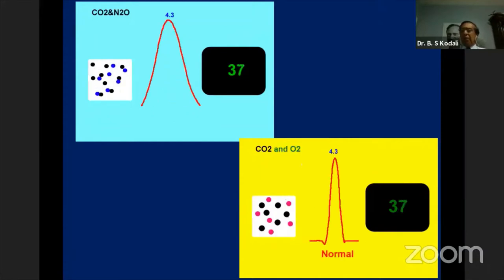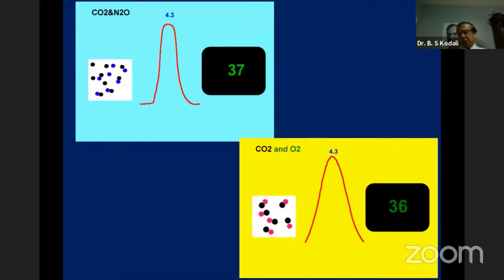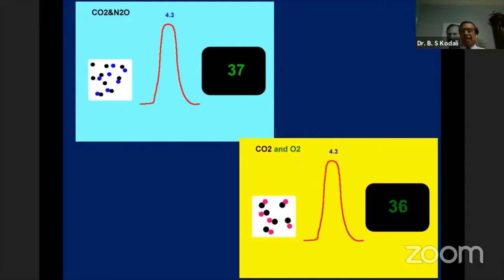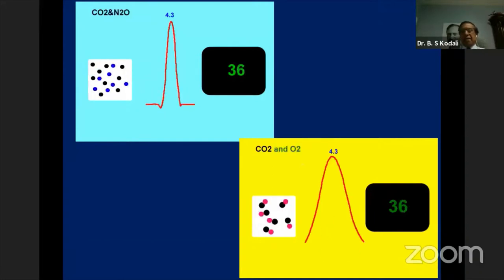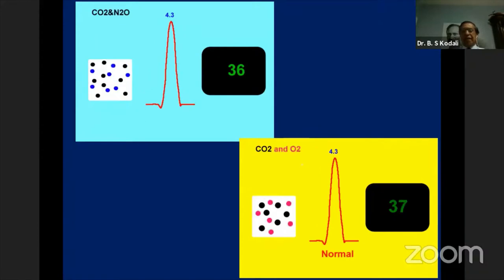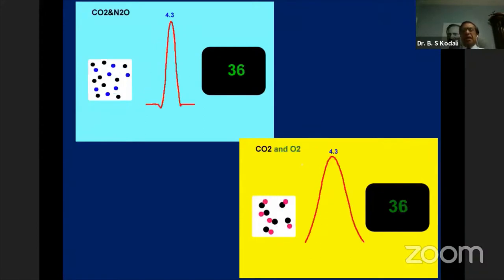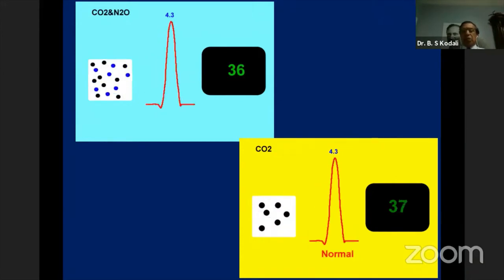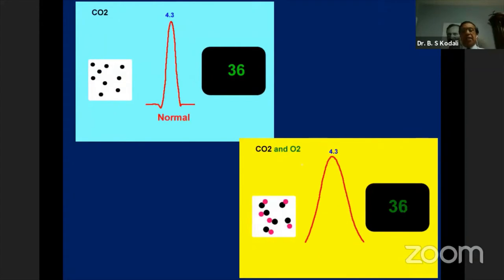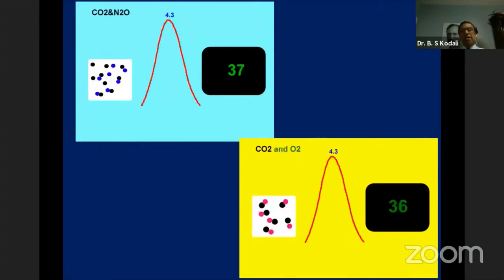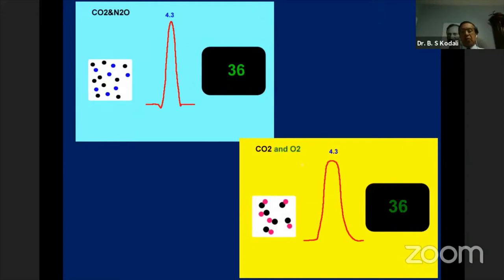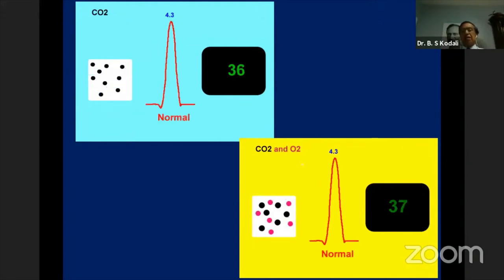In clinical use, the errors produced by these interference effects are minimal, so we need not worry about them in clinical practice. However, if you are doing a physiological experiment, you have to remember to account for the interference of nitrous oxide, water vapor, and the collision broadening effect, and give corrections for your measurements.